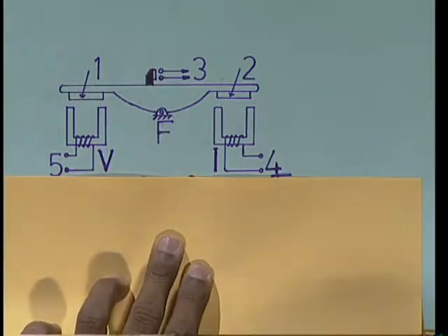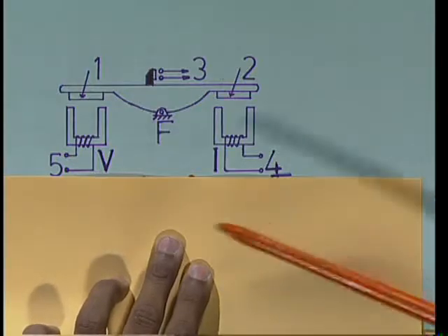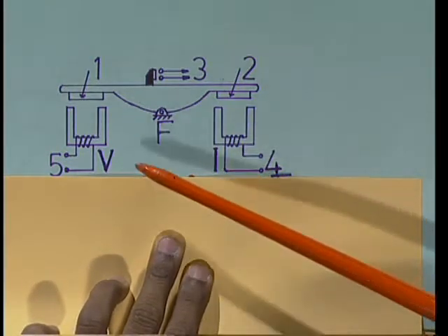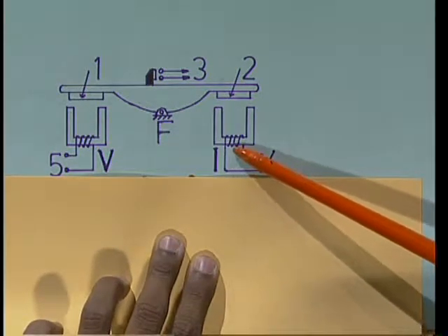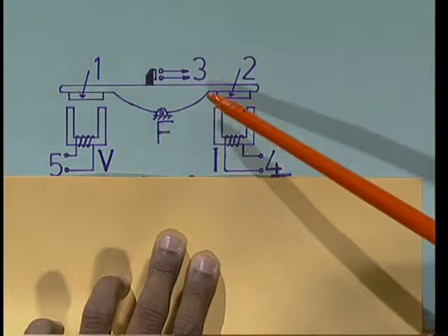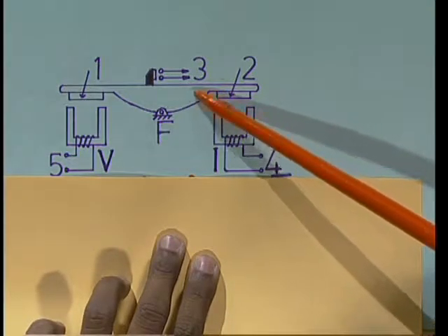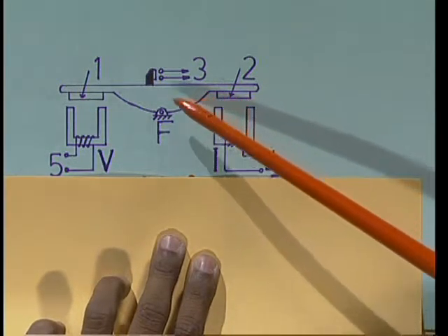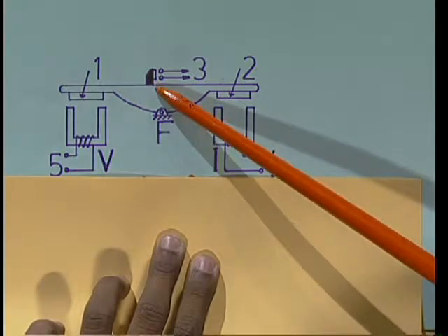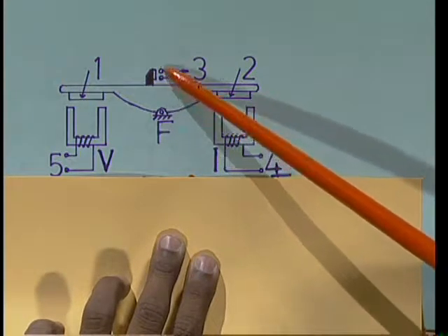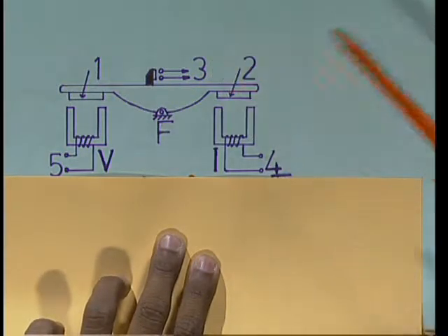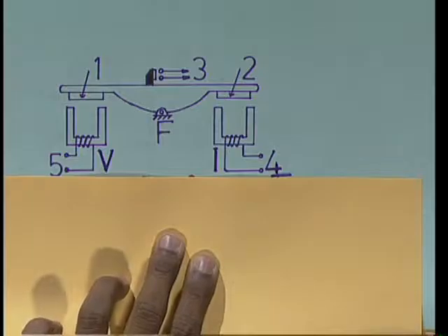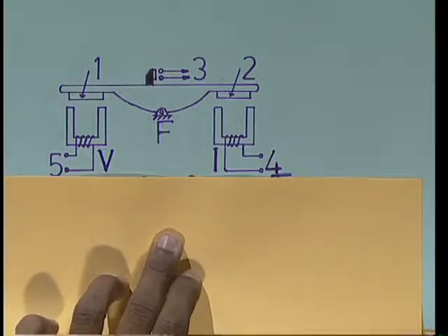Short circuit conditions. That means the voltage decreases, current increases. In this way the pull of the voltage decreases, the pull of the current increases. So the beam is tilted in the current direction. The moving contact also moves and touches the two fixed contacts, and it closes the trip circuit. Then the trip circuit energizes the circuit breaker, and this circuit breaker disconnects the faulty section.